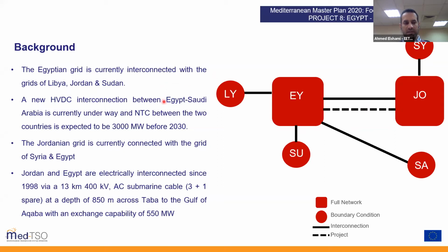As for the Jordanian grid, it's currently connected with the grid of Syria and also Egypt. Jordan and Egypt have been electrically connected since 1998 with a 13 kilometer submarine AC cable at 400 kV. The cable consists of 3 circuits plus 1 spare, at a depth of 850 meters, crossing from Taba to the Gulf of Aqaba in Jordan.